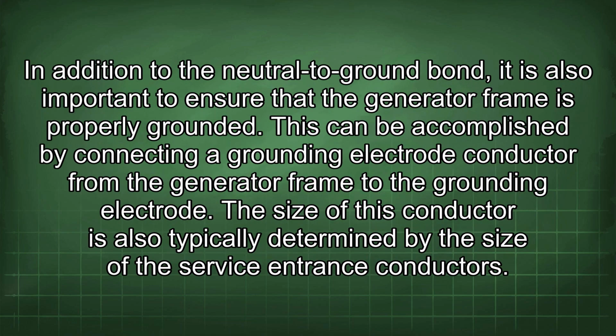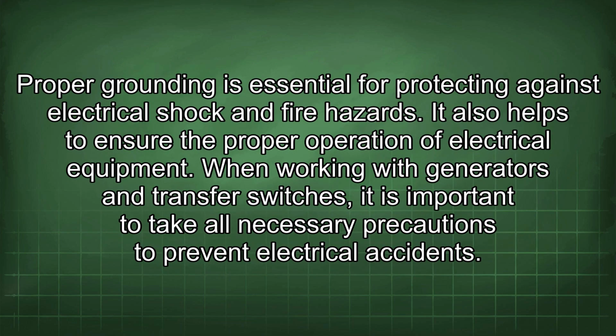In addition to the neutral to ground bond, it is also important to ensure that the generator frame is properly grounded. This can be accomplished by connecting a grounding electrode conductor from the generator frame to the grounding electrode. The size of this conductor is also typically determined by the size of the service entrance conductors. Proper grounding is essential for protecting against electrical shock and fire hazards. It also helps to ensure the proper operation of electrical equipment.